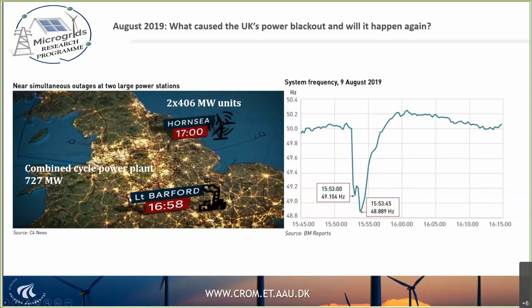You can see a combined cycle plant from Barford. It was shut down—727 megawatts—at 2 minutes to 5. Then, 2 minutes later, an offshore wind farm with units of 406 megawatts, around 8 megawatts each, went down as well. You can see here the effect: the frequency was 50 hertz, and suddenly, when the combined cycle plant went down, the frequency dropped.